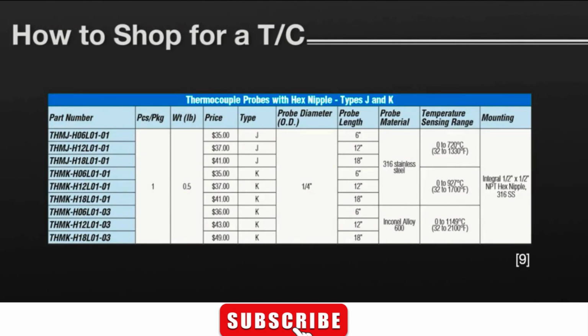The Type J probe can only measure up to 720 degrees C. This is a little lower than the 760 degrees C shown on the ITS 90 spec. Some manufacturers will quote a lower maximum temperature for thermocouple if they think they can't hold the full accuracy spec throughout the range. The Type K probe will work reliably up to the upper range of its calibration, in this case 1149 degrees C, but only if you specify the Inconel material for the probe sheath. The 316 stainless steel probe sheath would corrode at this temperature and ruin the thermocouple inside.